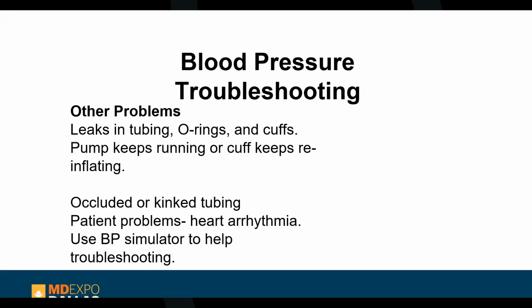That luer connector is the part where the metal piece tends to go bad. It's one of the top things we replace when there's an error that keeps pumping. The other cause, if it keeps pumping, is a bad pump motor. That motor doesn't put out enough millimeters of mercury to reach the pressure it's supposed to stop at and then start coming back down.